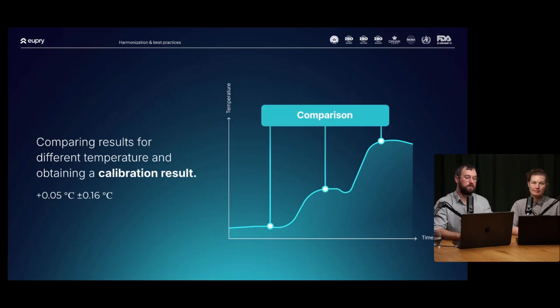There's always going to be uncertainty when we talk about calibration. We can never be absolutely sure about the result. And how to choose that calibration uncertainty and the criteria for when we accept or reject a calibration for a process, we're going to talk a lot more about. But the key thing here to remember is that every calibration result must have an error of indication or a calibration error. It can have a lot of different names. And an uncertainty attached to it. If it does not have both, it is not a calibration result.